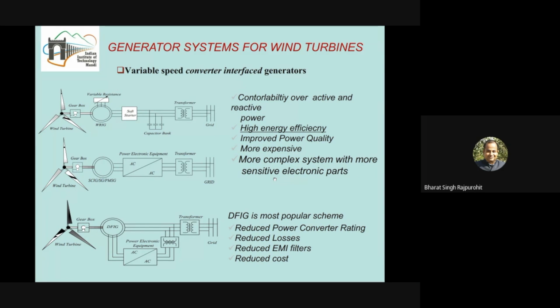Now the middle scheme has the same arrangement for a squirrel cage induction generator, synchronous generator, or permanent magnet synchronous generator, where the stator is connected to power electronic equipment. Different types of configurations are possible, but ultimately the AC is being generated by the stator. This AC is of a different frequency and different voltage level. It is converted from AC of different voltage and frequency to alternating current of the desired level and desired frequency, as per the grid connection.